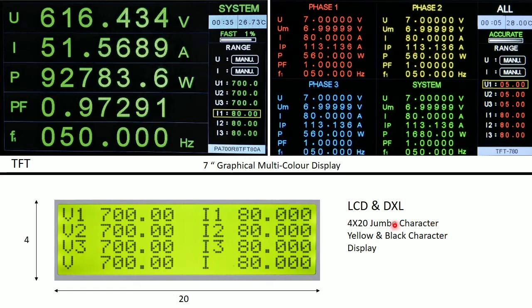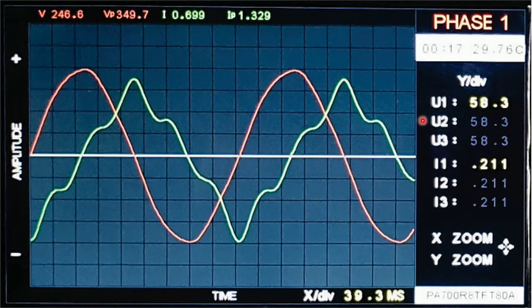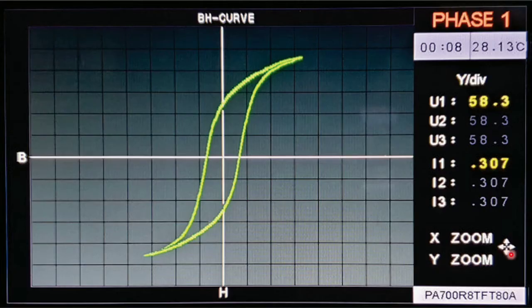Regarding type of display: a 7-inch graphical multicolor display is provided in the TFT model only, whereas the LCD and DXL models have a 4×20 jumbo character yellow-and-black character display. Because the TFT model has a graphical display, it can show waveform and BH curve modes. This is the waveform mode shown on the TFT model — this is the waveform of phase 1. You can zoom in and zoom out using the up, down, left, and right keys. This is the BH curve of phase 1.